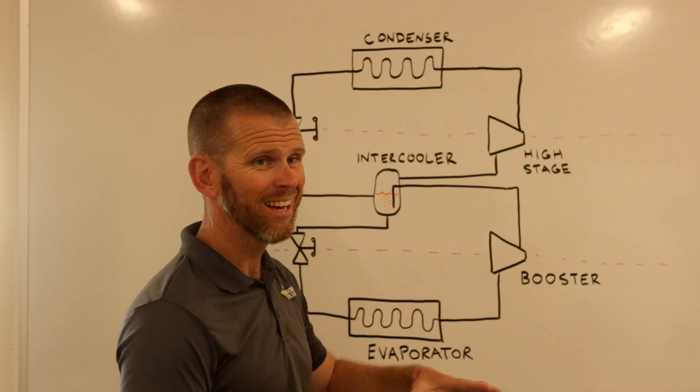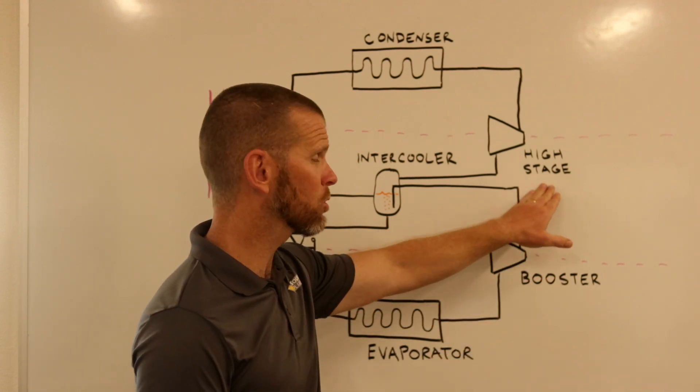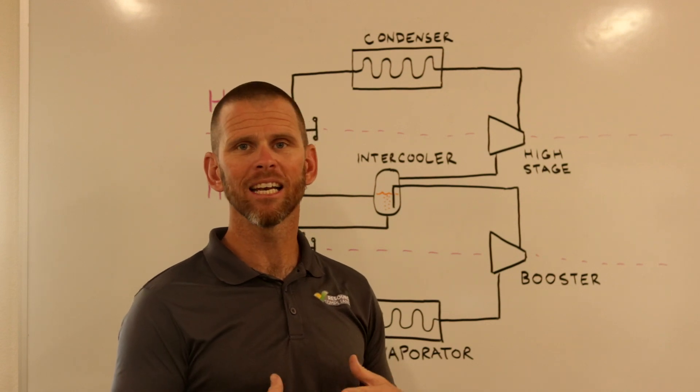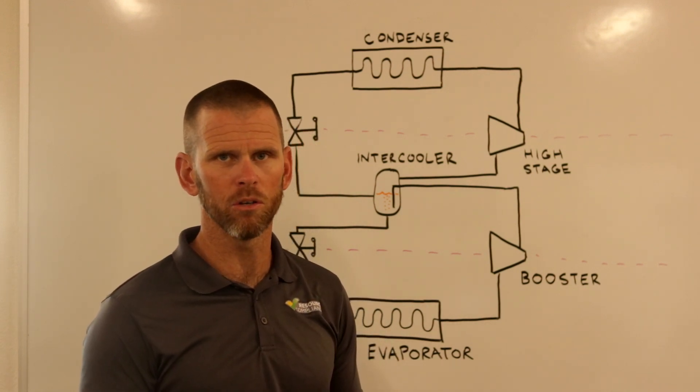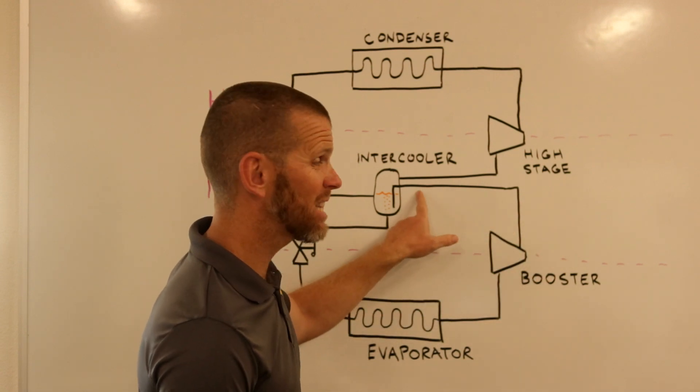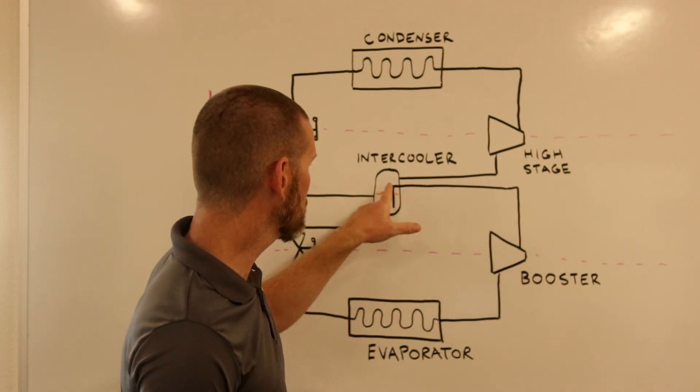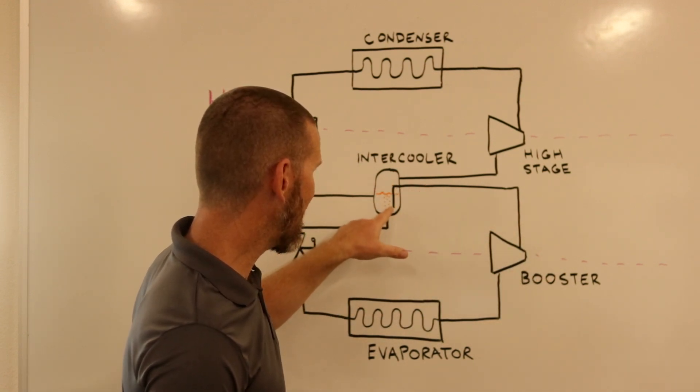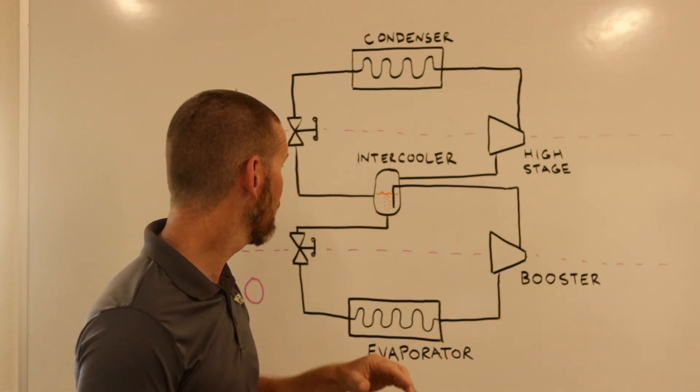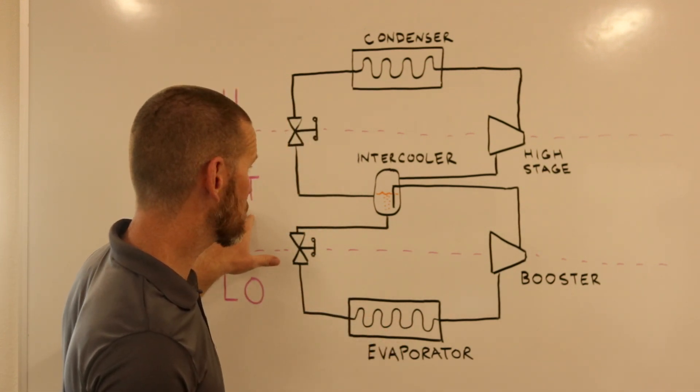The booster compressor functions very similar to a high-stage compressor, except that the discharge from the booster doesn't go to the condenser like we're used to. Instead, the discharge from the booster compressor is piped to the intercooler. I'm showing the pipe here going down to the bottom of the intercooler into that bath of intermediate pressure liquid.